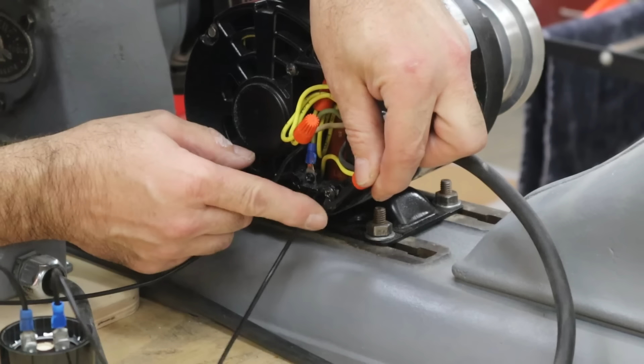Here's the capacitor. We calculated for a capacitance of 82 microfarads. I went locally and was able to purchase this capacitor from an HVAC dealer, but the only thing is that this capacitor is actually rated in a range from 72 to 88 microfarads. With capacitors, they have a tolerance of about plus or minus 20%. This is all that was readily available.